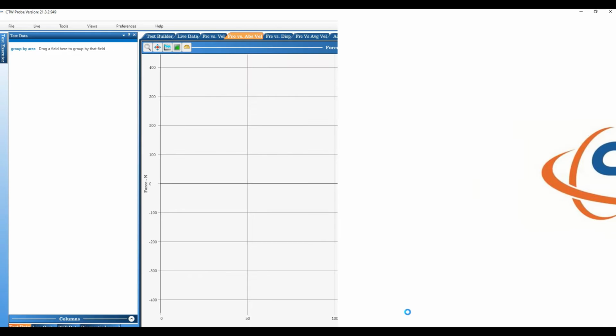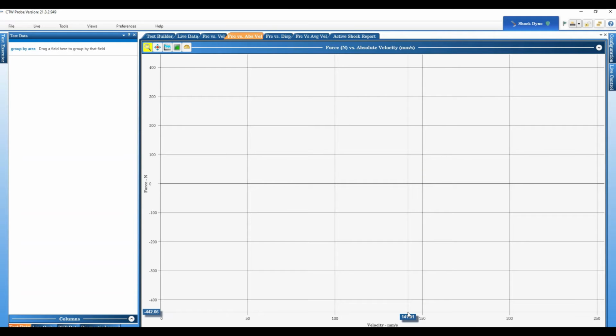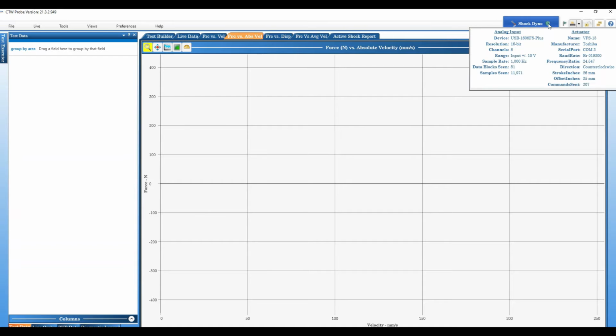They are not generic, is the key there. All right, so once it's loaded, hopefully you have a green shield up here, and if we look at the green shield, analog input, that's basically a technical term for the data. So that's the data card, and the actuator is the motor. If they're both counting, you're in very good shape, and they are.